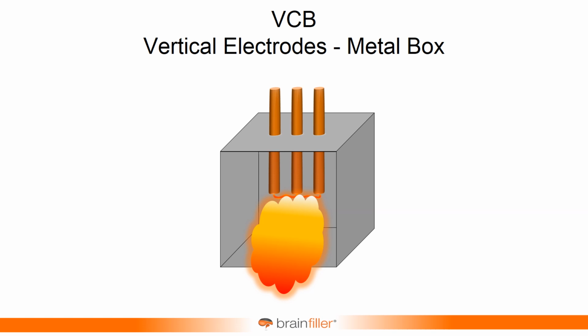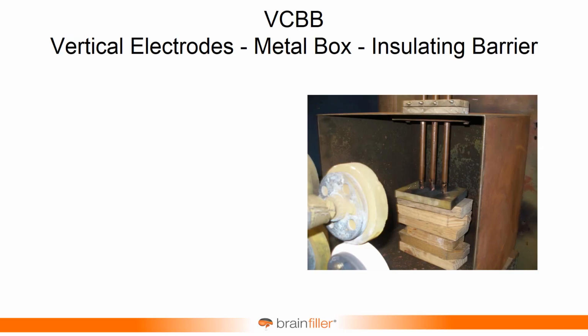And that's the test that we had in 2002, and basically repeated it, refined it, but repeated it. So we still have that configuration for the next edition. And then we have a configuration for the insulating barrier. Now this was a test setup from several years ago. Again, this isn't the exact setup from the new standard. There are pictures for those test setups that you'll be able to see with the new standard. But it's pretty much the same kind of idea.